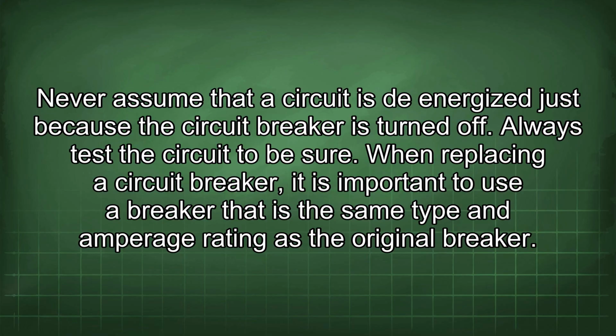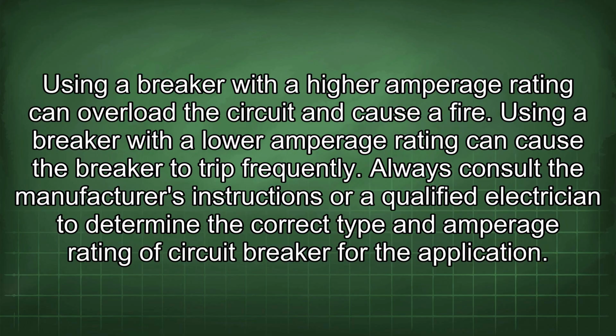When replacing a circuit breaker, it is important to use a breaker that is the same type and amperage rating as the original breaker. Using a breaker with a higher amperage rating can overload the circuit and cause a fire. Using a breaker with a lower amperage rating can cause the breaker to trip frequently. Always consult the manufacturer's instructions or a qualified electrician to determine the correct type and amperage rating of circuit breaker for the application.